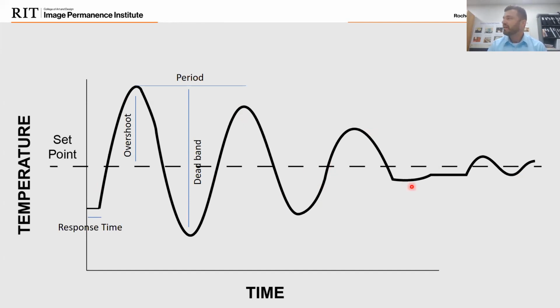If you reduce the deadband, does that reduce the overshoot? Is there a way to minimize the overshoot? It depends on your system. Some older systems we've seen can't change that. But if you reduce the deadband, you can reduce the overshoot as well.